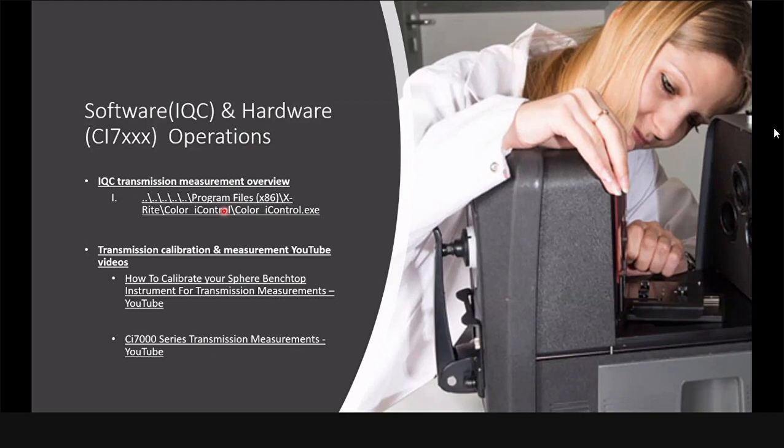So what do they normally do now? What is their basic requirement? I can help you, Naem, because the 361T is a transmission densitometer, and this device is using a reflectance mode.